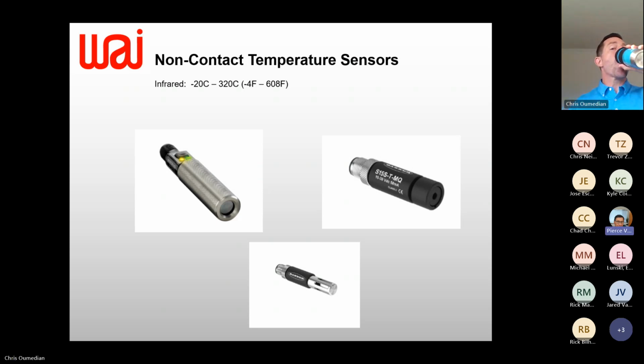This sensor at the bottom where you have temperature and humidity. Mm-hmm. I need to talk to you about that because right now I'm wrestling with large electrical enclosures that have to be kept above the dew point. Yes, exactly. And the two determining factors for dew point are temperature and relative humidity. They are. And so we can do exactly that, Pierce, with this device. We also have, which I did not include in this presentation, a dew point sensor with Banner Engineering. No way. Yes, sir. So give me a call afterwards.